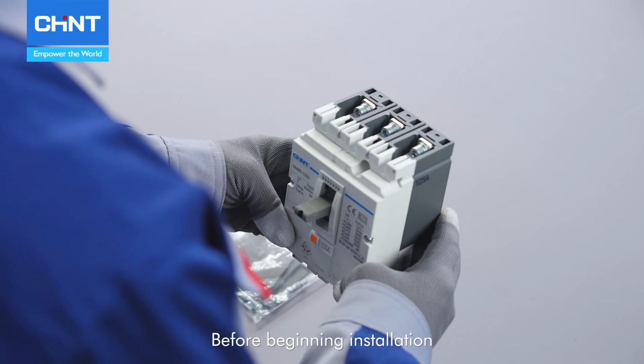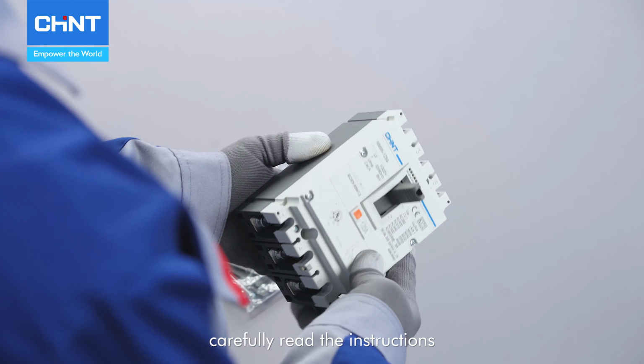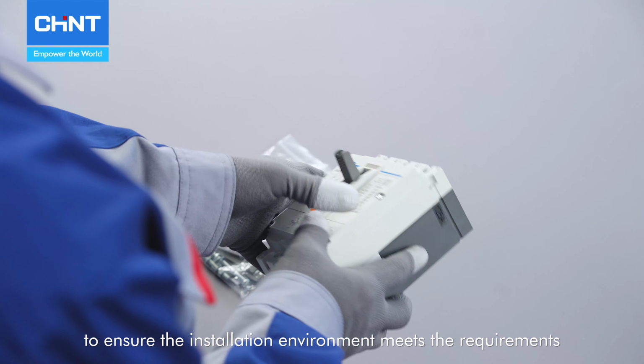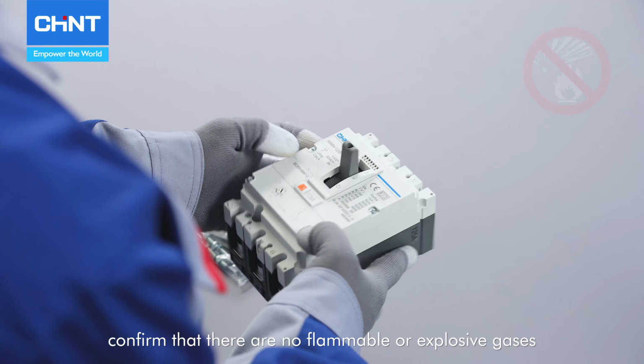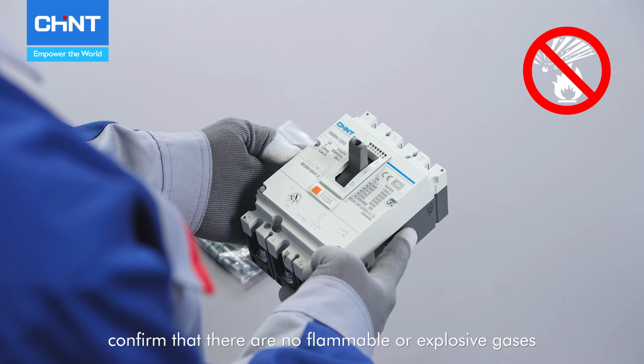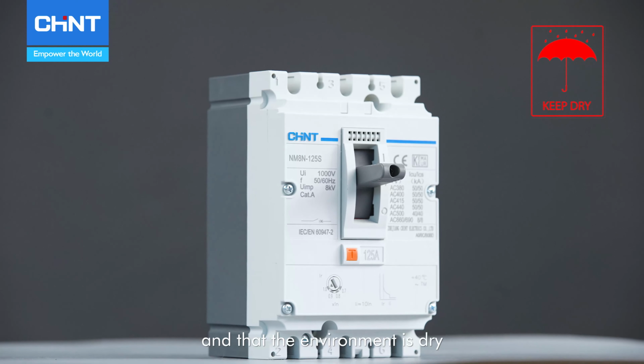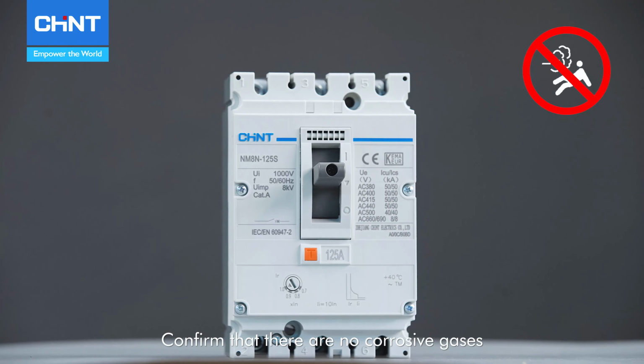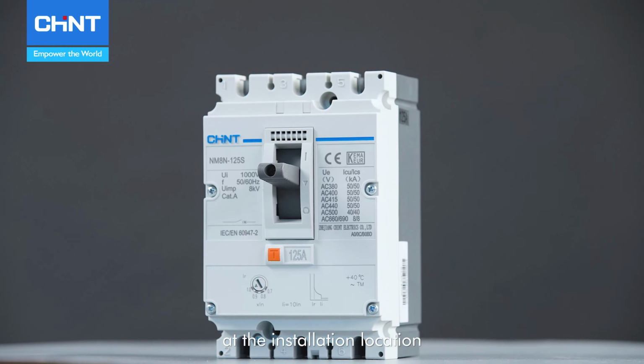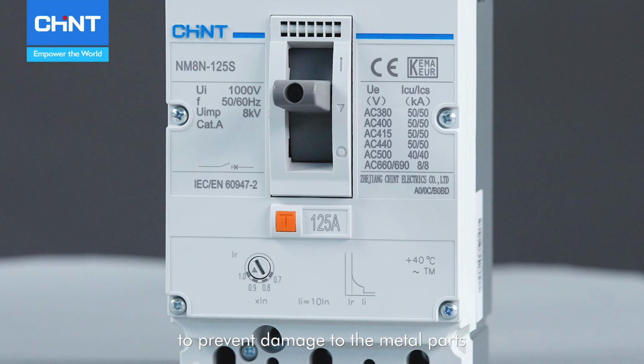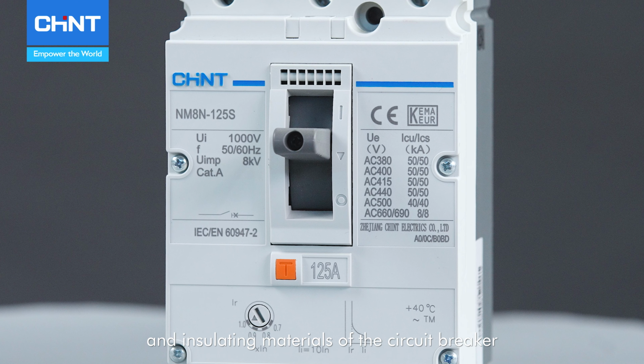Before beginning installation, carefully read the instructions to ensure the installation environment meets the requirements. Confirm that there are no flammable or explosive gases, and that the environment is dry. Confirm that there are no corrosive gases at the installation location, to prevent damage to the metal parts and insulating materials of the circuit breaker.